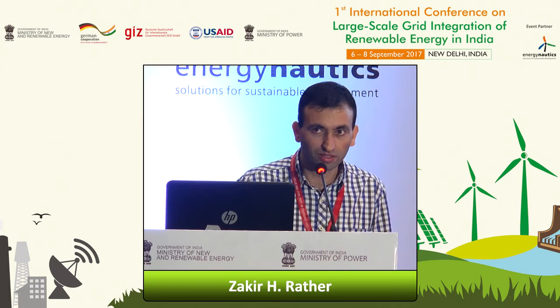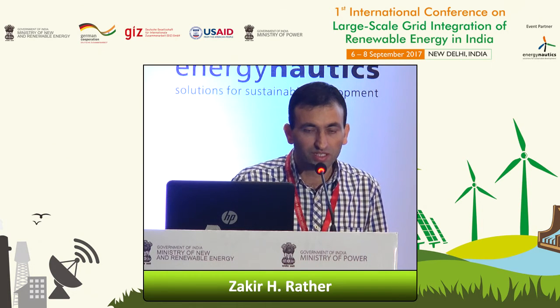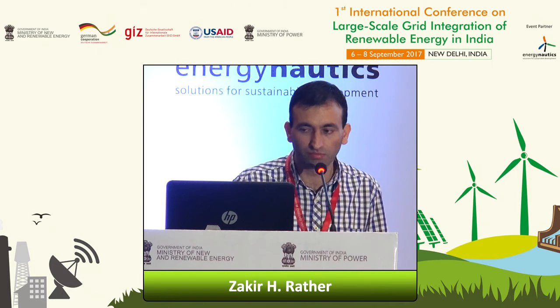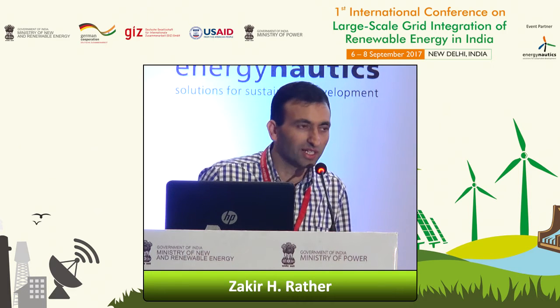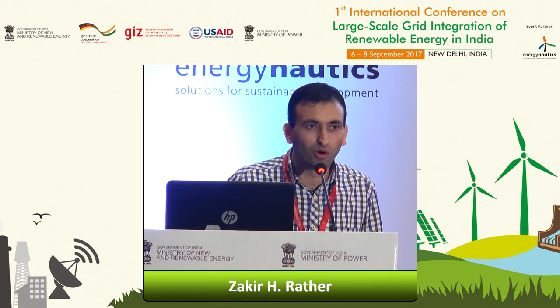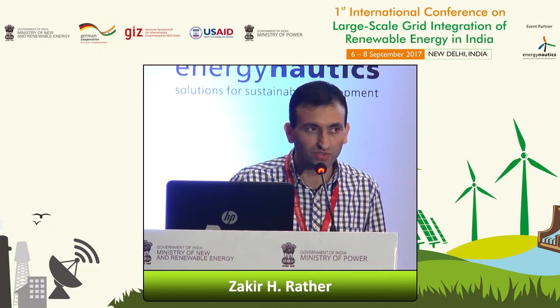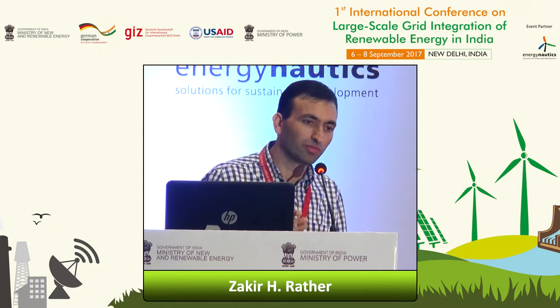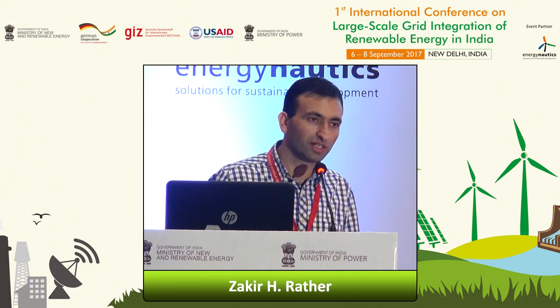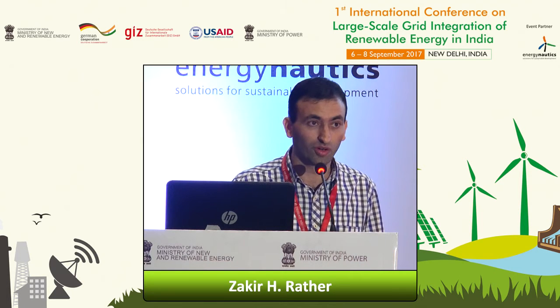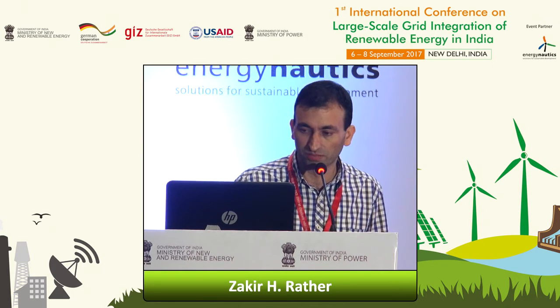If it is an RMS system stability study, then probably we may not need to take into account the entire electromagnetic transient part. Same goes for, let us say, steady state analysis, where we don't need the detailed modeling which is actually necessary for EMT analysis or harmonic analysis. So it is also very important what type of study we do, and we have to select the model accordingly. And I don't think we can have a single model fitting all these possible studies.